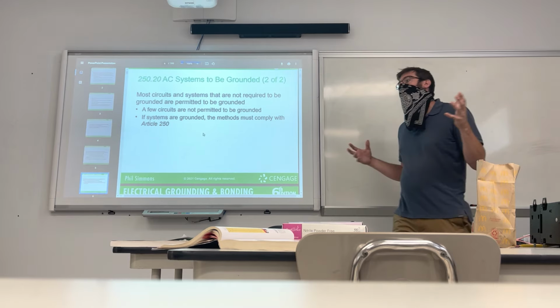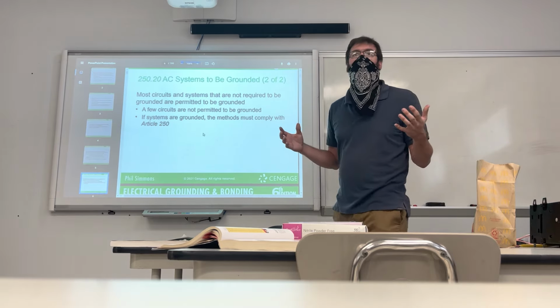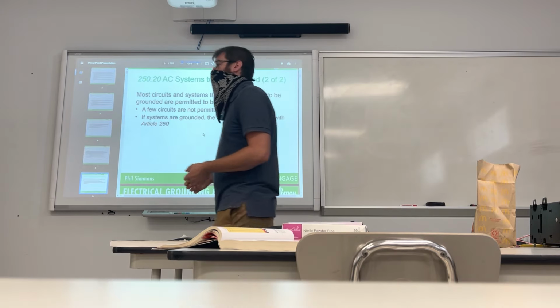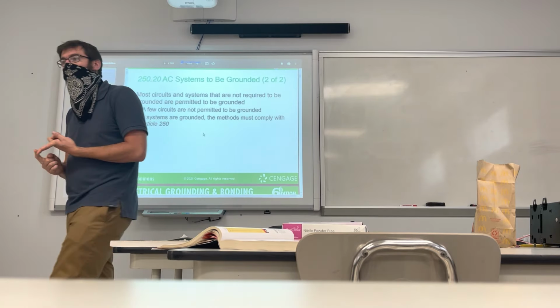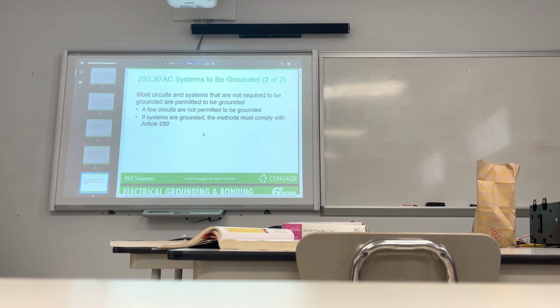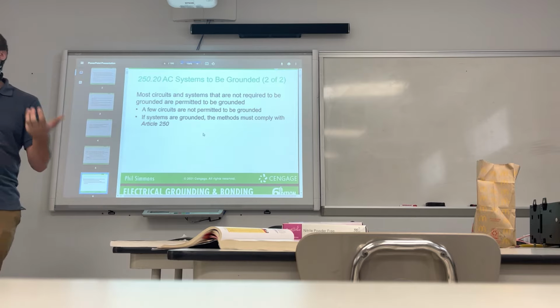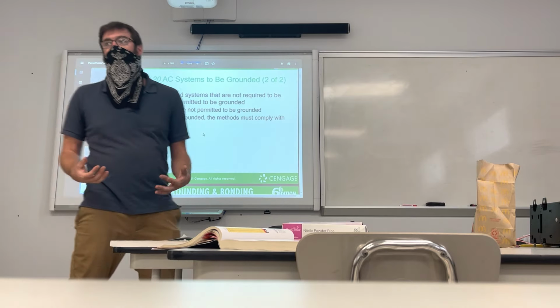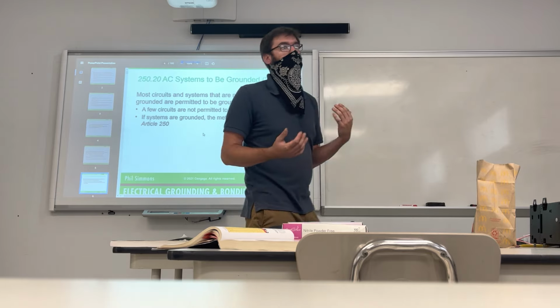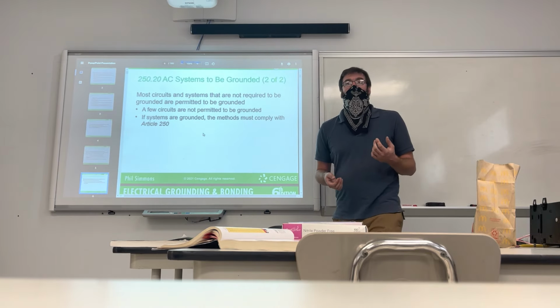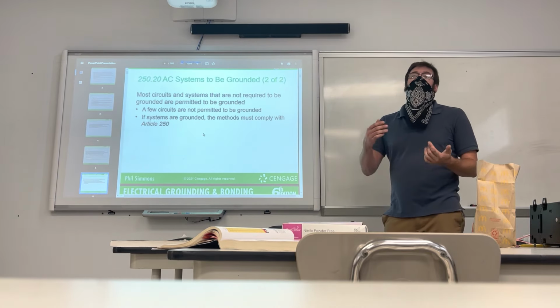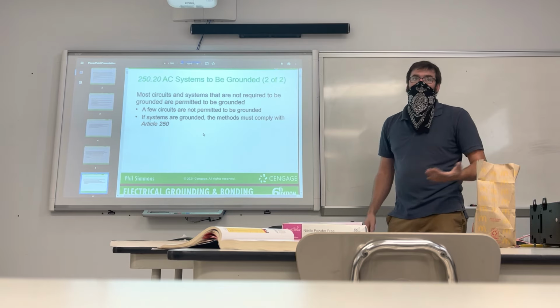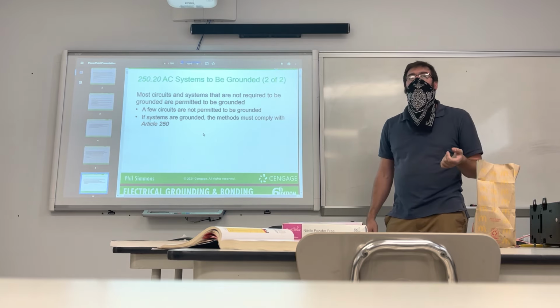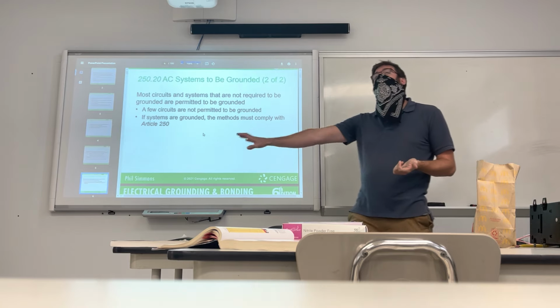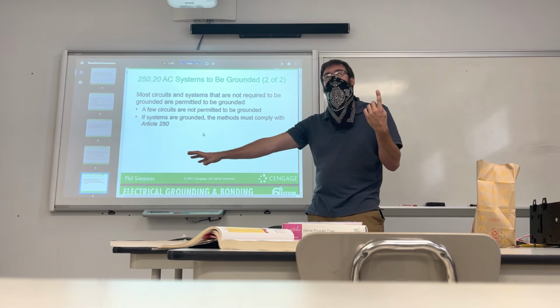So now we have a huge, huge three-phase motor running something. It's running a blower for a furnace to melt steel. It's running a big motor keeping a conveyor going throughout an entire factory or possibly an airport terminal. Something huge. Something that you don't want to fail. Even if it starts acting up, you don't want it to fail completely. So what they'll commonly do is they'll put an alarm on each piece of conduit. So if that alarm senses, hey, we have power running through this conduit, that machine is going to continue to run, because on one short, it's not going to fail.